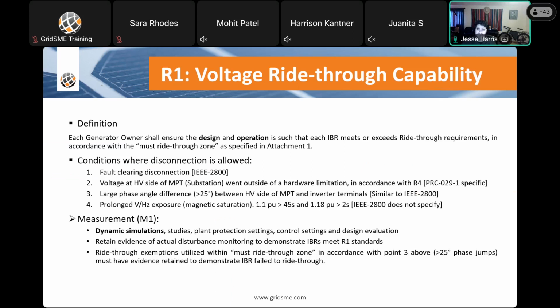Requirement R1 is the voltage ride-through capability. This is fairly similar to what is in place right now with PRC 24-3. And it says that each generator owner shall ensure the design and operation is such that each IBR meets or exceeds ride-through requirements in accordance with the must ride-through zone as specified in attachment 1. Notice the bold there on the design and operation. You see this throughout requirements 1, 2, and 3. And it's a very important concept within PRC 29, which I'll cover in a little bit.